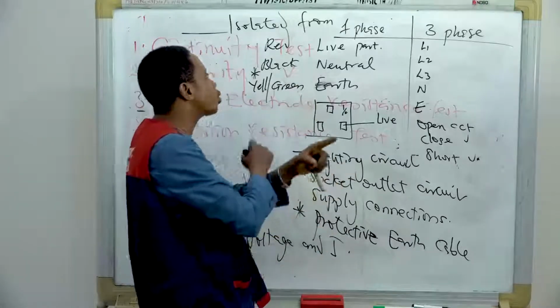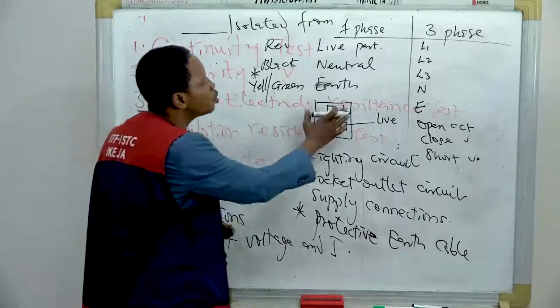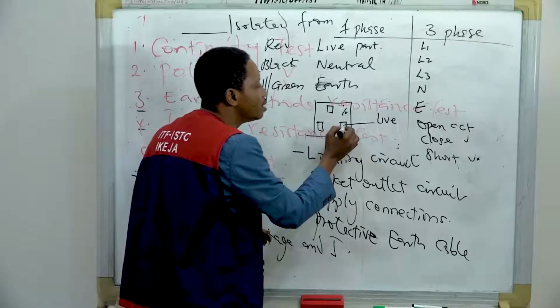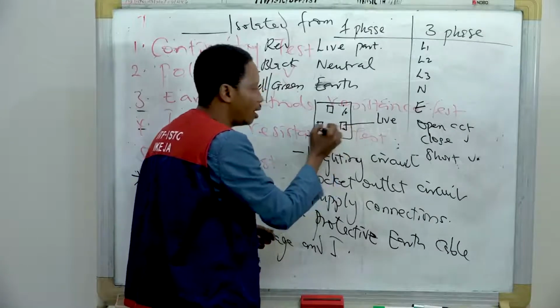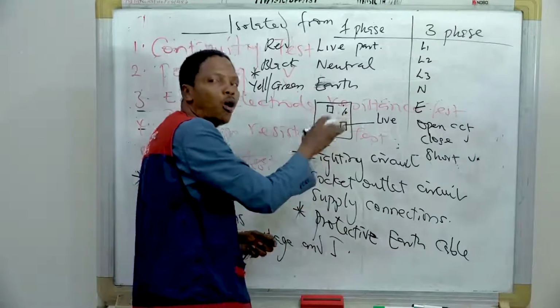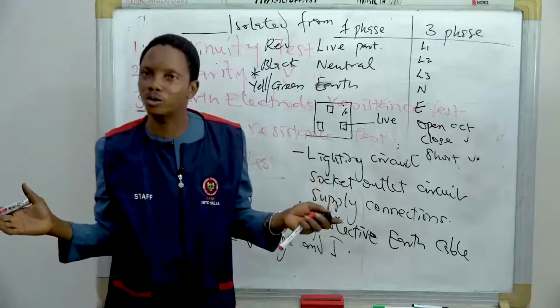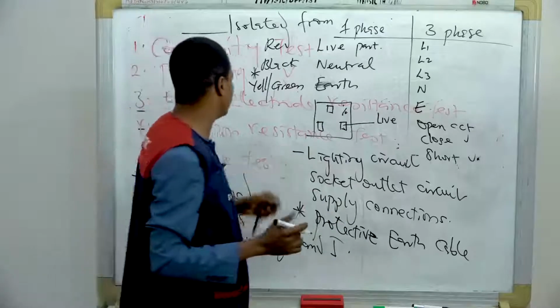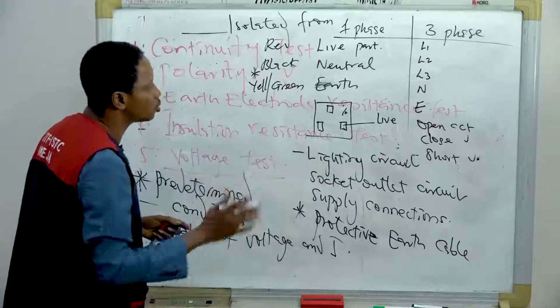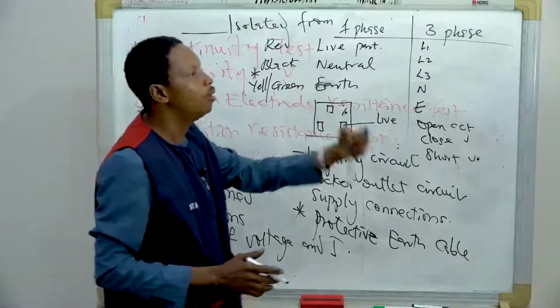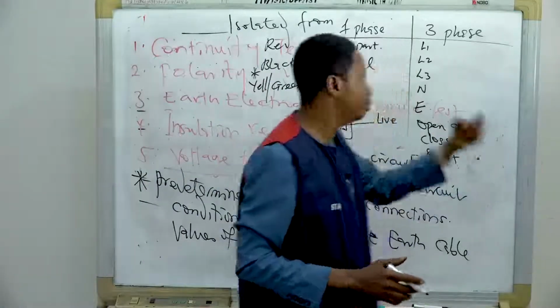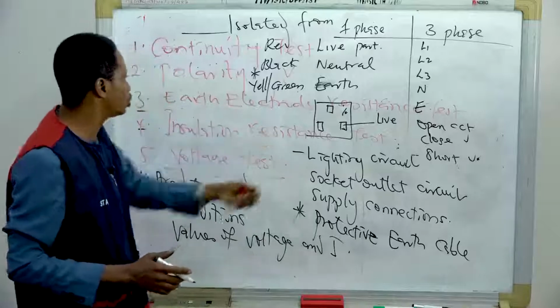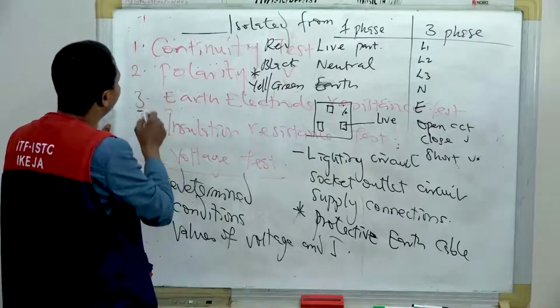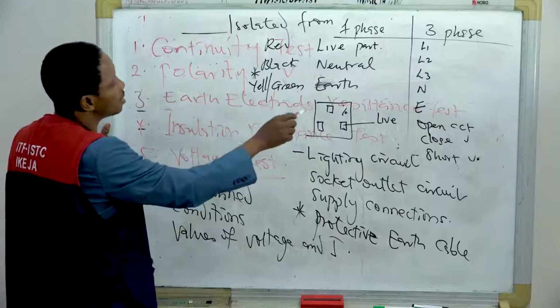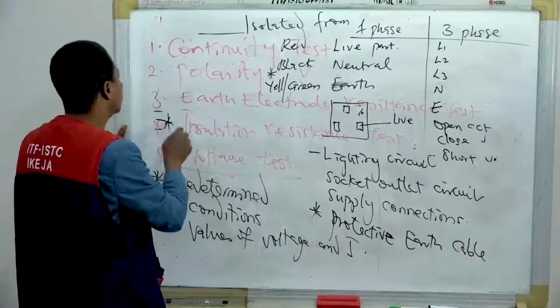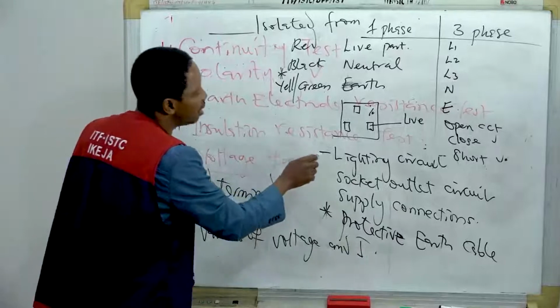Now, if you have a wrong polarity, when you put off this switch, this is having neutral, this is having live. So when you off it, the circuit is not totally off. It's only the neutral that is off. So that polarity is wrong. That is why we must ensure continuity and polarity. Continuity, we ensure. Now, the next one, before I explain earth electrode resistance test, let me quickly talk about insulation resistance test.